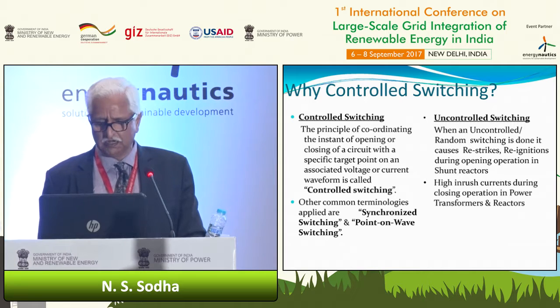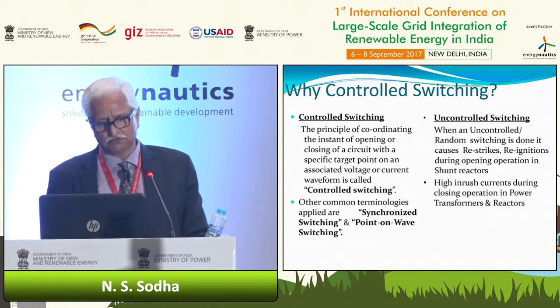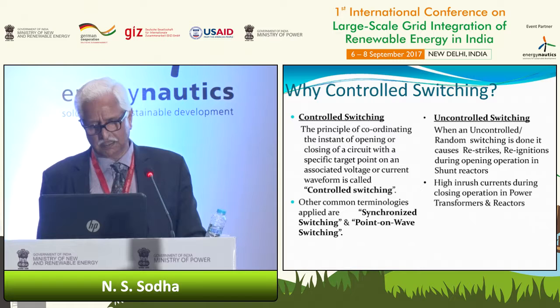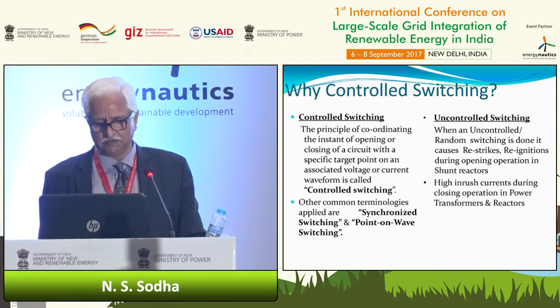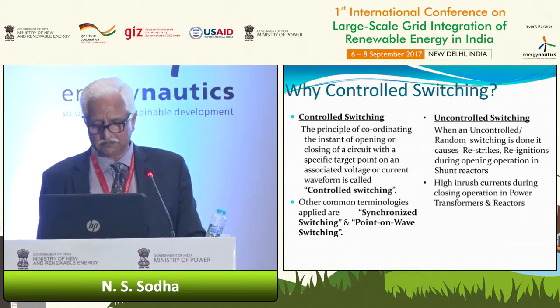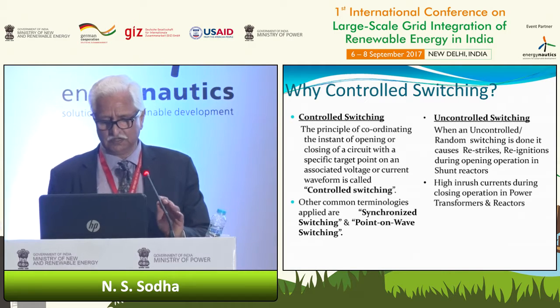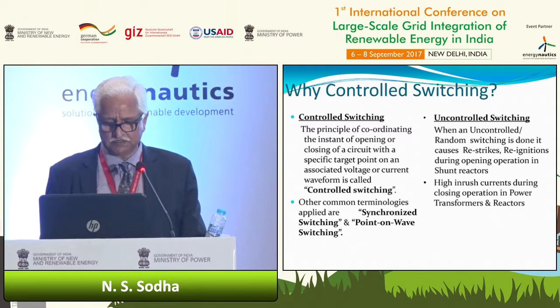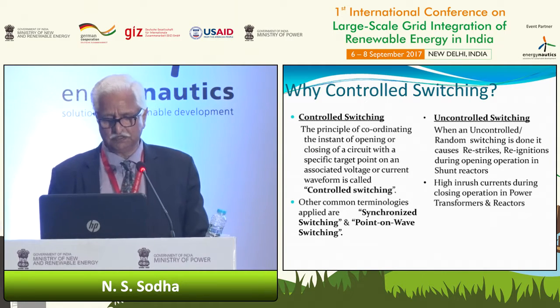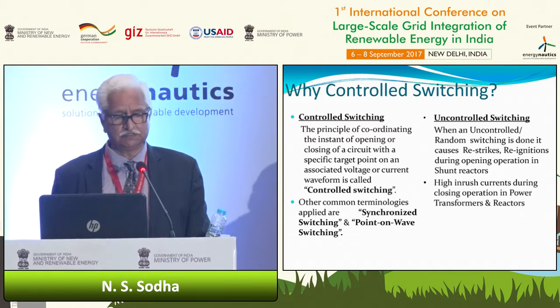Now, in the earlier time, we used to have no control switching, and uncontrolled or random switching causes restrikes and reignitions during opening operations in the shunt reactors, and high inrush currents during the closing operation in the power transformers and reactors.